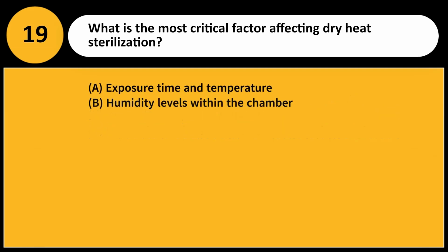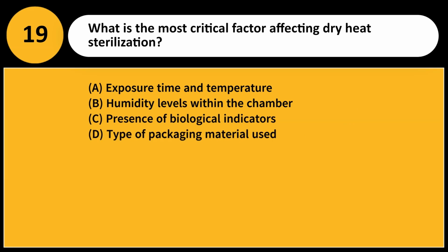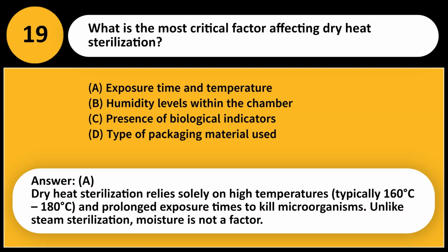What is the most critical factor affecting dry heat sterilization? A. Exposure time and temperature. B. Humidity levels within the chamber. C. Presence of biological indicators. D. Type of packaging material used. Answer A. Dry heat sterilization relies solely on high temperatures, typically 160 to 180 degrees Celsius, and prolonged exposure times to kill microorganisms. Unlike steam sterilization, moisture is not a factor.